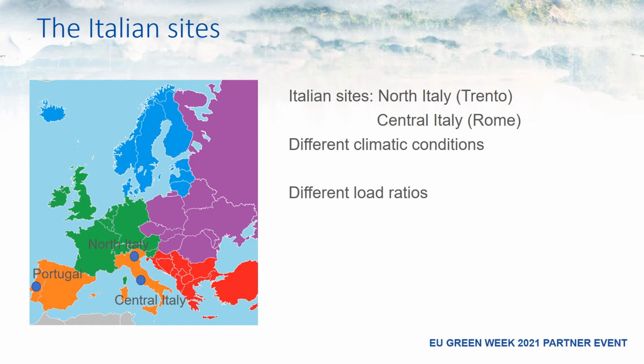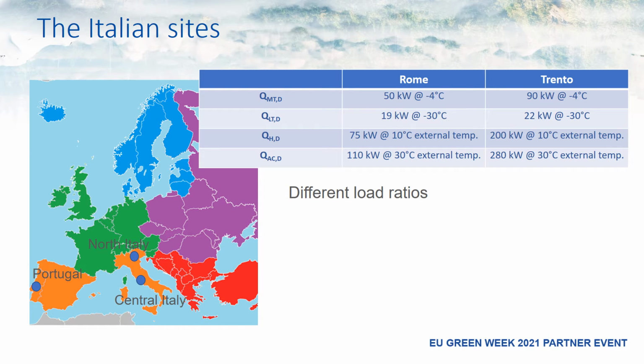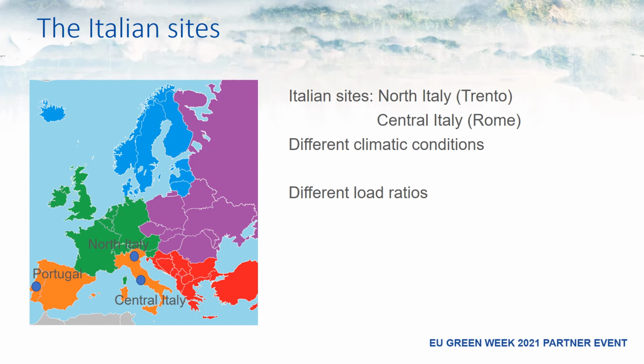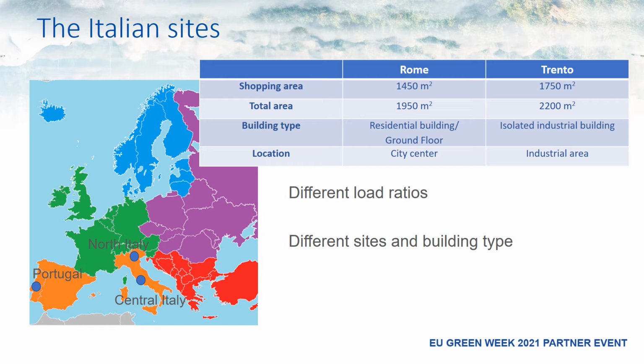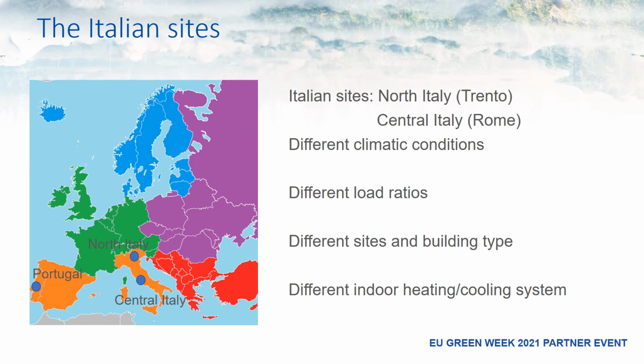These two sites have also different load ratios, so the demands for refrigeration, heating, air conditioning are completely different, and this is also going to impact on the performance of the system. The sites are different, but also the building types are different, and in particular, the site in Rome is a residential building, so the supermarket is on the ground floor of a residential building located in the city center of the town, while in Trento, the building is an isolated industrial type building, so different locations, different types of buildings, and also different indoor heating and cooling systems.